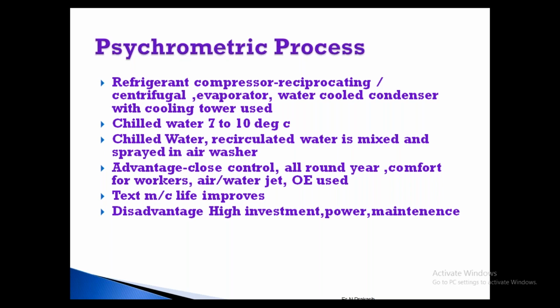So in the chilled water system, what I was explaining earlier was normal water that we use for the spray chamber. If you are using chilled water, that means involving a refrigeration compressor, an evaporator, and a water-cooled condenser, so there is going to be power on that. The water will be chilled and circulated in the air washer. Irrespective of the outside dry bulb, wet bulb, and RH conditions throughout the year, if you want to maintain all-round air conditioning for the entire year without any disturbance, then you have to go for a chilled water air washer. So that becomes all-round air conditioning, but it is used only in certain places. It improves the textile machine life, but the disadvantages are high investment, more power, and more maintenance.